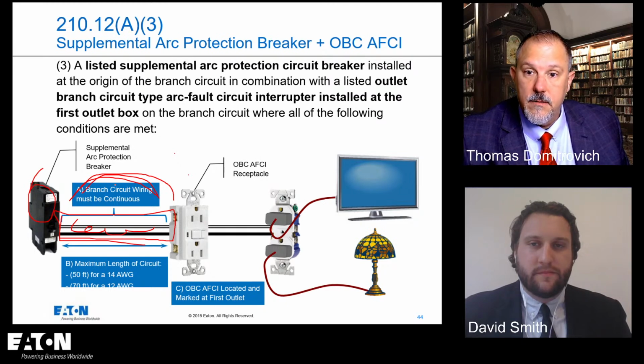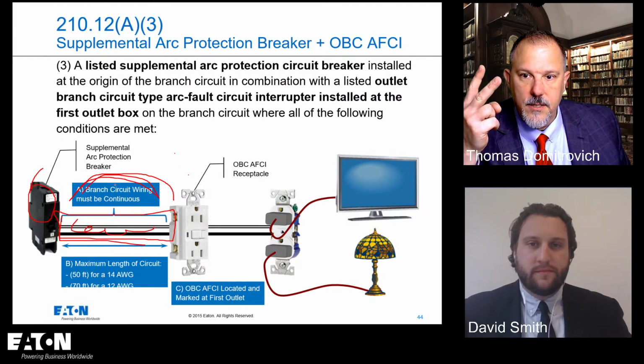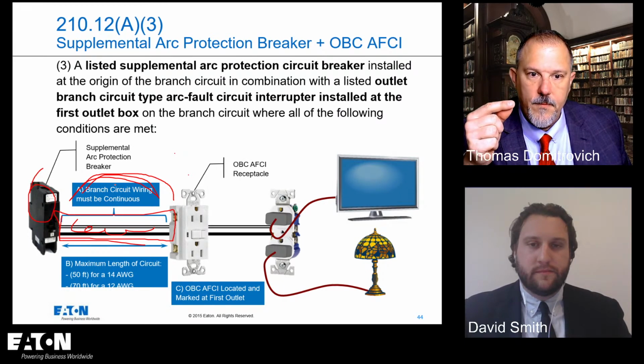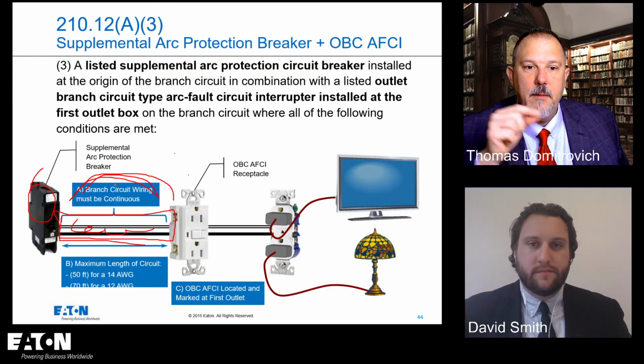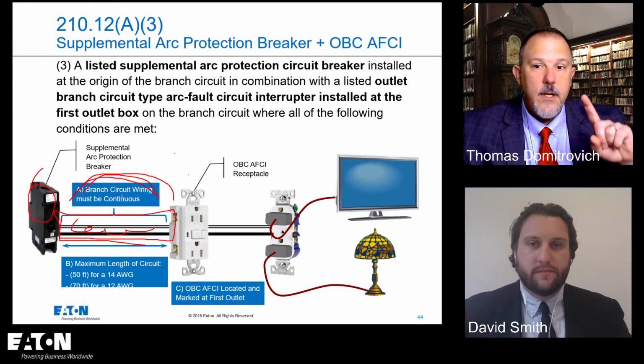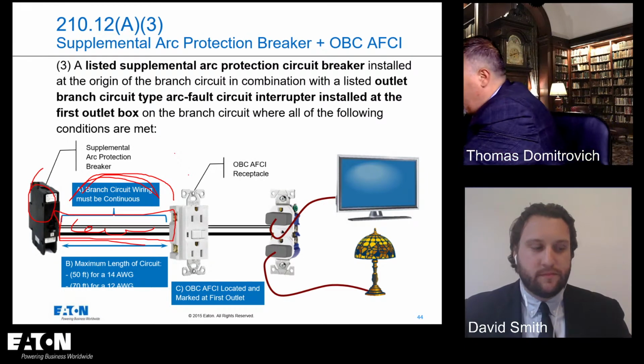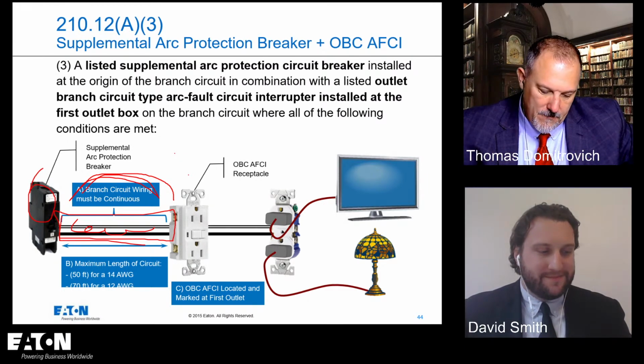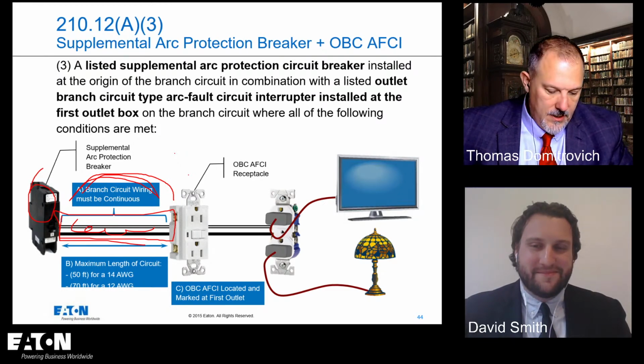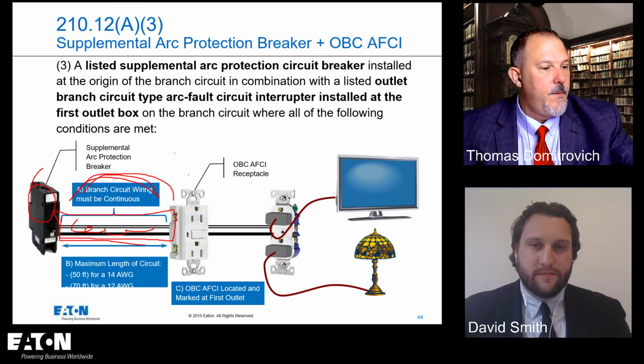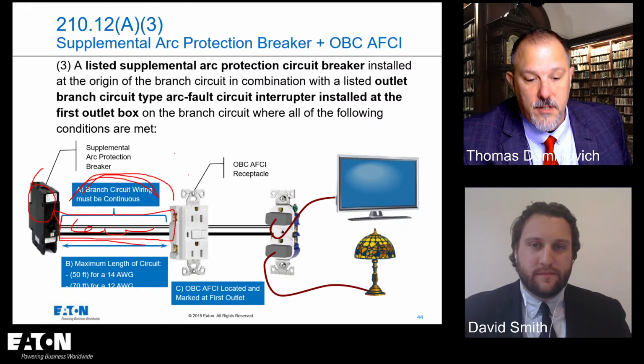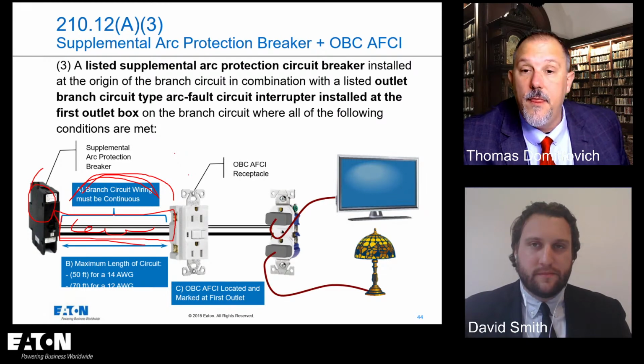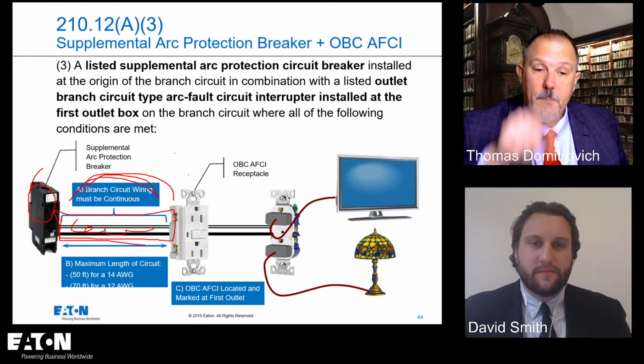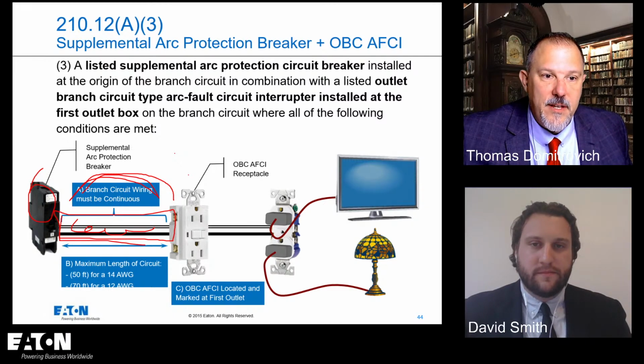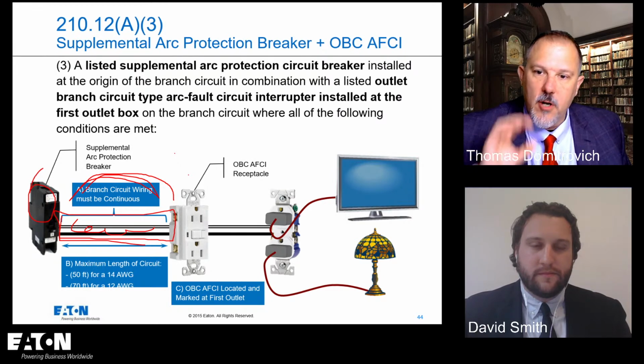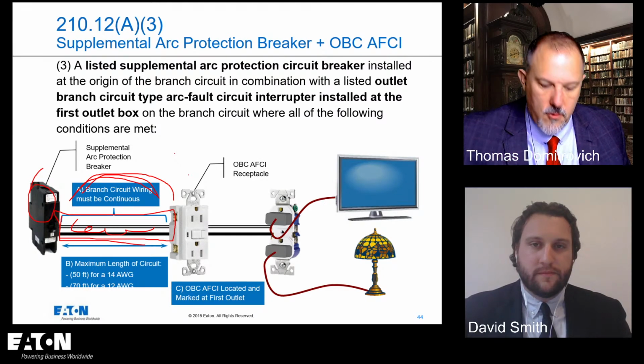UL did studies. They did 2 studies. The first one they published wasn't quite right. They missed a couple important details. And the title of that study, that's why I got my papers out. The title of that was Effectiveness of Circuit Breakers in Mitigating Parallel Arcing Faults in the Home Run, because that's what they're debating. Panel 2 was saying, look, what can this circuit breaker actually detect from an arcing perspective in the home run circuit? What's the vulnerability there?